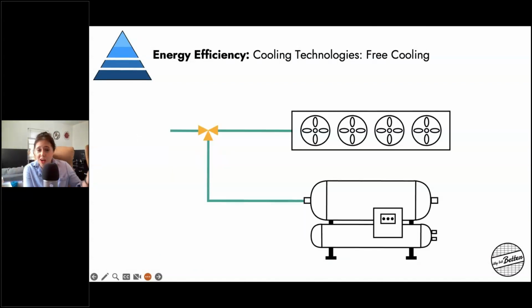Focusing on those CRAH units, free cooling is one of the biggest things being pushed in the data center industry right now. Again, coming back to that psychrometric chart and increasing that inlet temperature - if the outside air is cooler than your data center, let's utilize it. The free cooling system hooks up parallel with your chiller, and it can either work side by side with it by pre-cooling the incoming water, or work instead of the chiller if it's cool enough outside for your data center.